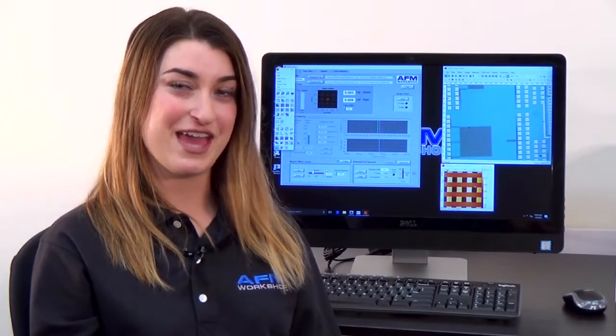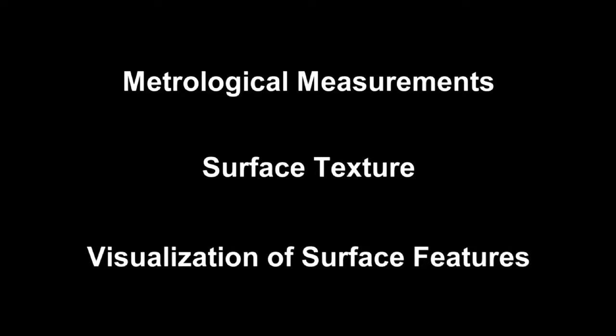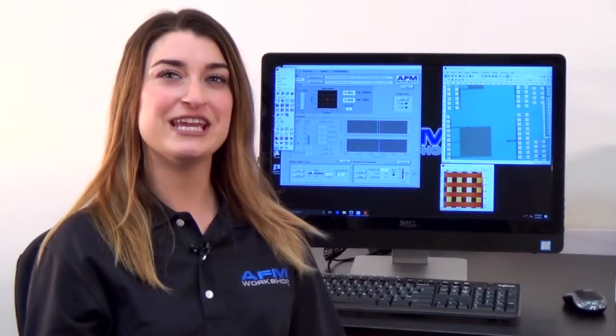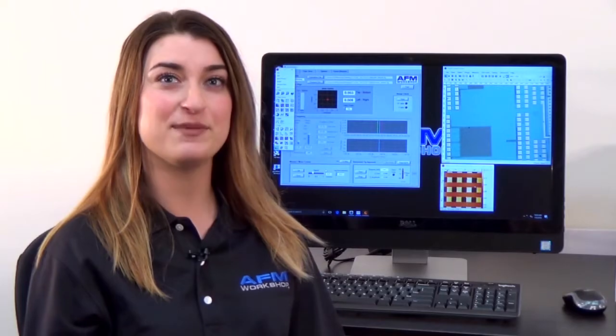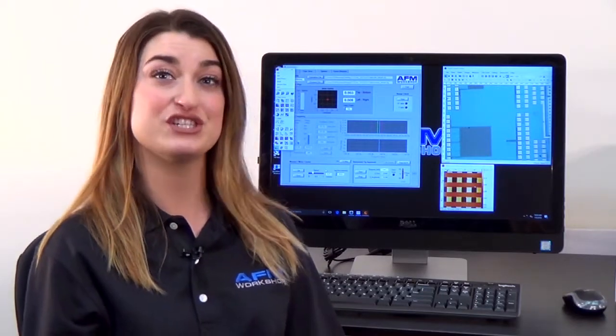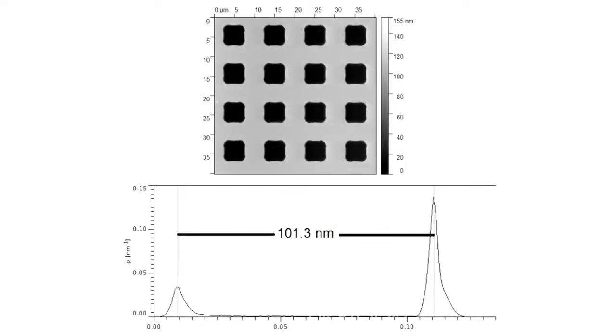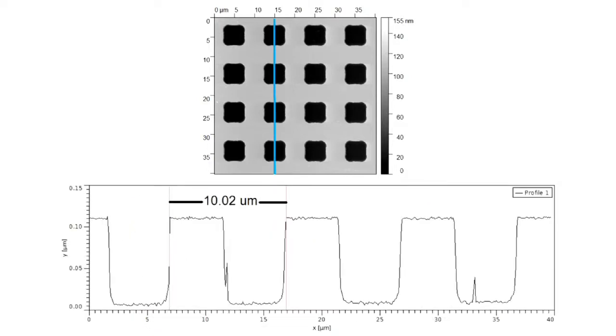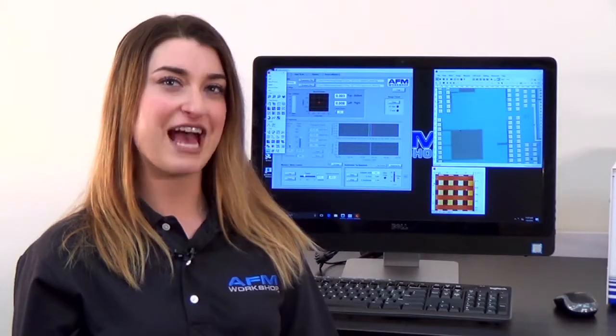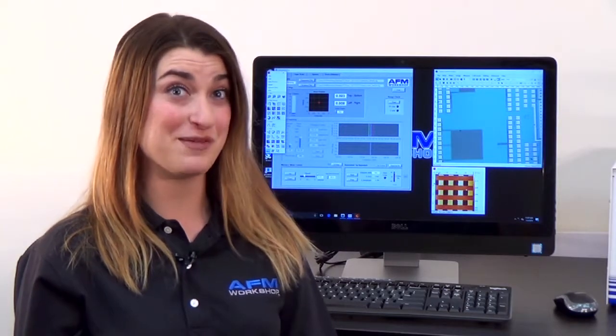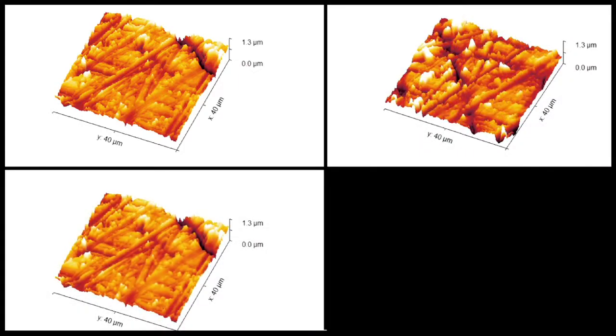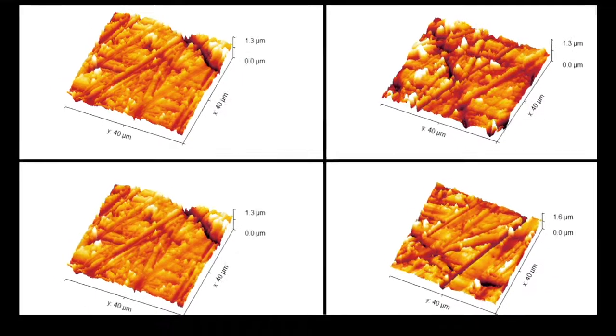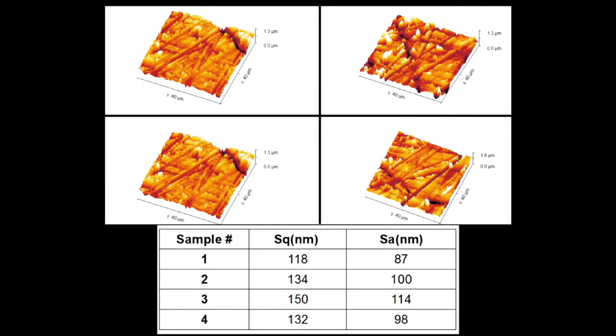Common applications for the NP-AFM include metrological measurements, surface texture, and visualization of surface features. With the unique piezoelectric scanner, the NP is ideal for measuring the dimensions of surface features. This includes surface heights as well as horizontal dimensions. Surface textures down to 150 picometers are measurable with the NP-AFM. With a vertical range of 17 microns, the NP can also give textures of extremely rough samples.